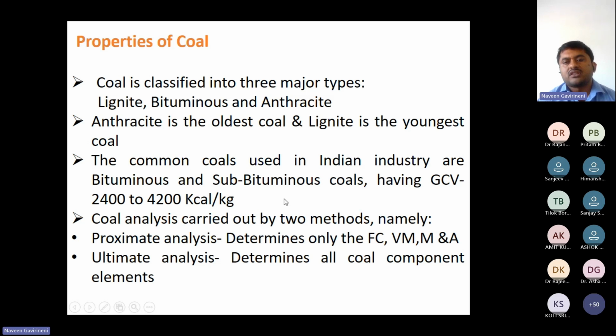We are getting bituminous coal. That range is 2,400 to 4,200. Now, we have designed, as mentioned by the OEM while supplying the boiler to us, for a GCV of 4,050 kilocalorie per kg. Again, this coal goes through analysis. There are two types of analysis: proximate analysis and ultimate analysis. These are the proximate analysis for the initial analysis. It gives fixed carbon, volatile matter, moisture and ash.